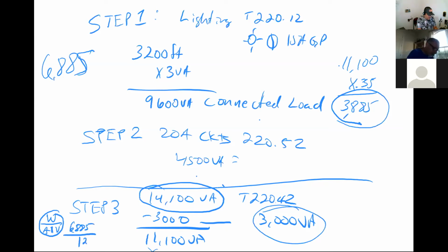So in this calculation, I could take that 6885 and put it over the 240 volts in a single family dwelling. That would give me the amps of those loads — not necessarily the service, but the minimum calculation. Now it comes out to be about 30 if even that: 6885 divided by 240 equals 28.68 amps.